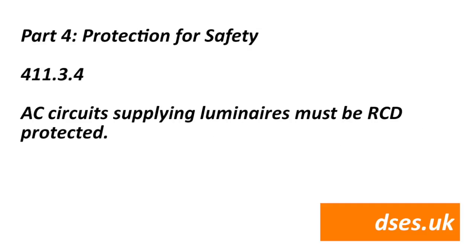Another change is Regulation 411.3.4, which now requires AC circuits supplying luminaires to be RCD protected. No real surprise — the use of RCDs has crept forward over previous amendments. By 17th edition Amendment 3, we were already obliged to RCD protect cables buried in walls at less than 50mm, and cables or accessories serving or passing through a room with a bath or shower. So new or altered lighting circuits may well have been RCD protected anyway, but now there's a specific regulation requiring it.